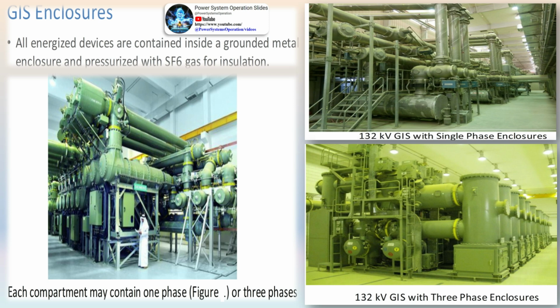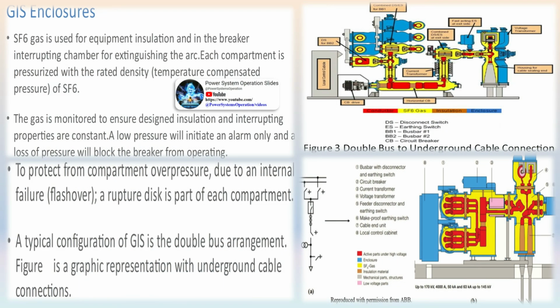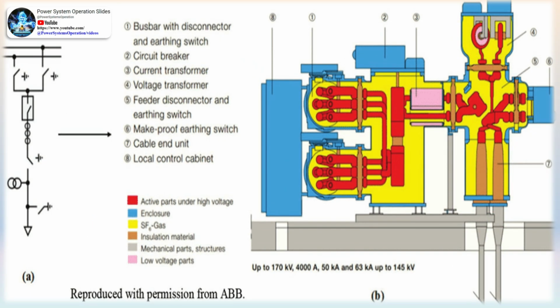Clearances for GIS are roughly a tenth of that for AIS. With GIS technology, the clearance needed for phase-to-phase or phase-to-ground for all equipment is much less than that of an AIS, or air-insulated substation. The total space required for a GIS is roughly a tenth of that needed for a conventional AIS facility. While the conventional AIS requires several feet of air insulation to isolate a conductor, SF6 gas insulation only needs inches, allowing a GIS facility to fit into areas far smaller than that of an AIS facility. A GIS is mainly constructed where real estate space is expensive or scarce.